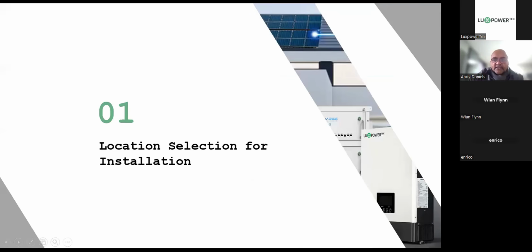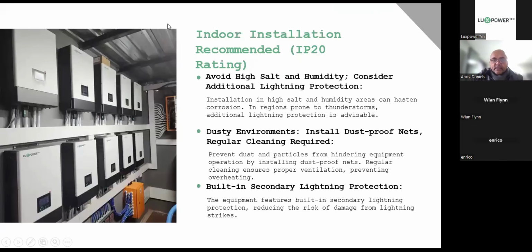Okay, right. So let's have a look at the typical type of installation that you're going to be doing. SNA is IP20 rated, right? It is not an IP65 like the LXP series, so you've got to be very, very careful on how and where you install it. First of all, coastal regions, not a favorite for the SNA. The reason being is the high humidity, the salt content in the air. It's definitely not the environment that we like to see our machine installed in, and certainly in our updated warranty documents, there will be a limitation on the location of the installation from the sea. So just avoid high salt and humidity areas.